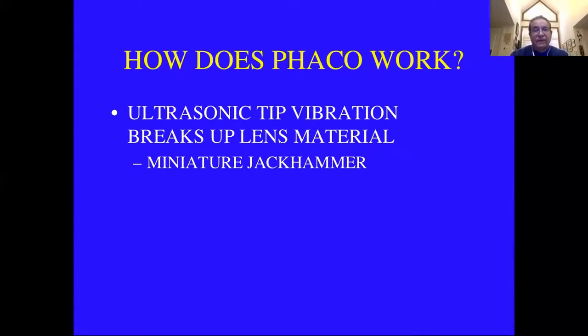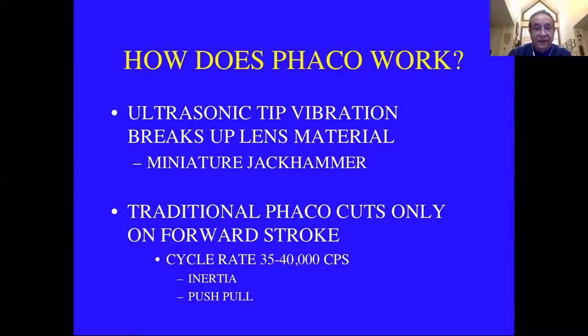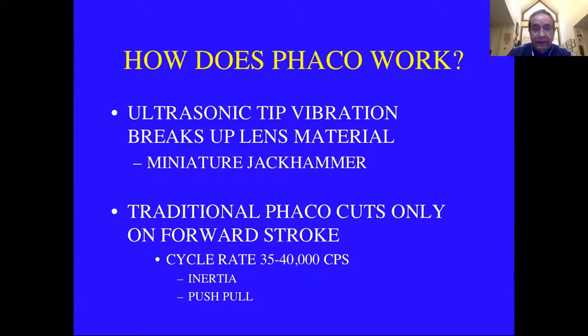How does phaco work? Basically, you have an ultrasonic tip which vibrates and breaks up lens material — it's like a miniature jackhammer. It moves forward and back very fast. You need a cycle rate of 35,000 to 40,000 cycles per second to overcome inertia. It only cuts on the forward stroke, then aspiration pulls the material back to the tip, and you get another forward stroke very rapidly, cutting into small pieces or emulsifying.